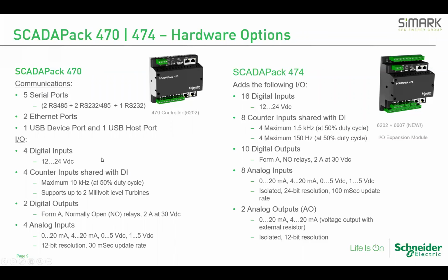The breakdown shown on the left gives you an idea of the I/O counts available on the 470 RTU. By adding in the brand new 6607 expansion module, packaging that together with the 470, we've come up with the 474 RTU, which adds 8 counter inputs, shared with the existing 16 digital inputs. We've added 10 digital outputs in the form of relay contacts, as well as supporting, straight out of the box, 2 analog outputs on the RTU. This is in contrast to the past, where analog outputs were an optional add-on purchased separately—now they're included with the purchase of the SCADAPack 474 without needing to specify them separately.